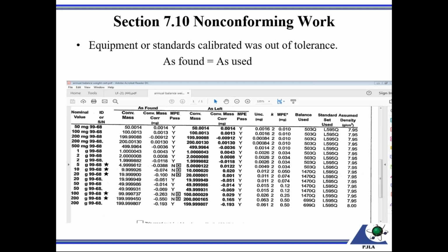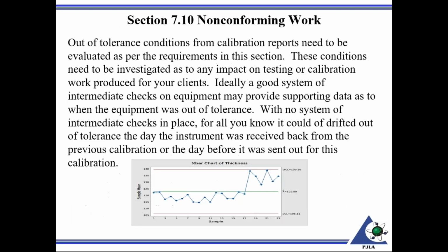So here's an example of a CalCert. Well, we have several as found failures. So this is outside of the specified tolerances. And hence what this means, and that's why I like to refer to it as used, that means the organization that submitted this artifact was actually using this artifact in that condition in producing customers' testing or calibration results. So when this happens, it needs to be evaluated as per these requirements.